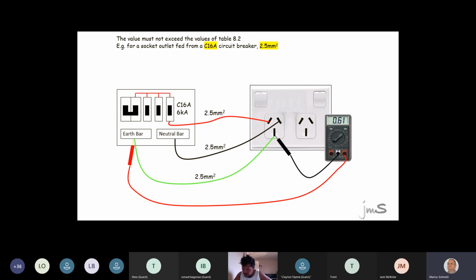If it's more than that, well, you're either going to lose connection, or your earth wire is too small. You probably have to upgrade to a bigger one. The length is too long. If the length is too long. Now, guys, you can work it out yourselves. Rho times length over A gives you your resistance. You all got your formula sheet with you somewhere.